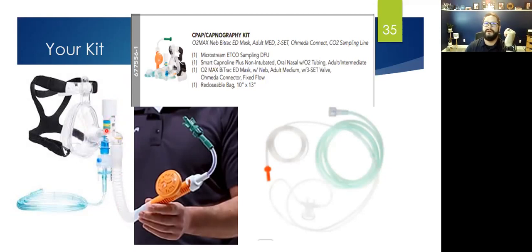What I want you to see is that for this picture, they turned it sideways so you can see there's three different numbers: 5 of PEEP, 7.5 PEEP, and 10. But the exhalation ports are actually on this side and that side. If it's twisted to this side, you're actually blowing air into the patient's eyes every time they exhale.